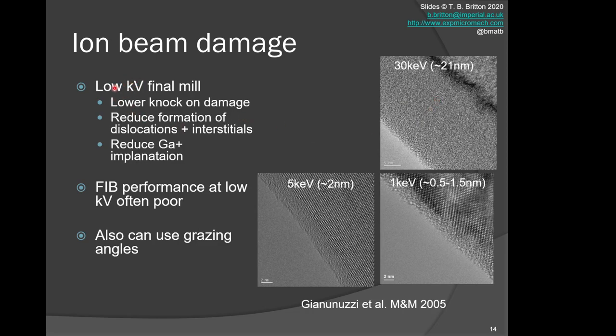This is why when we do sample preparation, we will often do a low kV final mill to reduce the knock-on damage, reduce the formation of dislocations and interstitials, and reduce the gallium implantation. We note, however, that most FIBs have poorer performance at low kV, so we will typically do incremental polishing—effectively high voltage and then step it down for the final polishing steps. In addition to reducing the polishing damage, we can do this at glancing angles. If you did direct implantation, it would cause a greater penetration depth, whereas if you did it at a high, steep angle, that will reduce the amount of surface damage as you're glancing away that surface of the material.